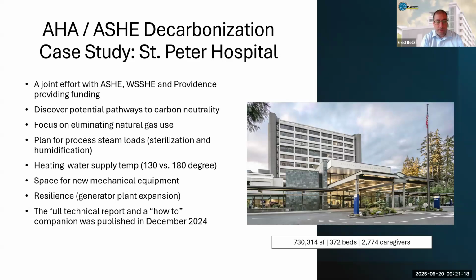We looked at 4 different pathways to carbon neutrality. We're going to go in depth on one today. You can look at the others in the study. The focus, as Kara mentioned and Jeff mentioned, is to eliminate the natural gas use, both the carbon emissions associated with combustion, but also the greenhouse gas emissions associated with methane leaks. So we really want to disconnect, which is a big challenge, especially in the light of processed steam loads, and we're going to address those. Hot water supply temperature, we're going to make a big deal out of that because that has a huge impact on electrification. We'll show you how.